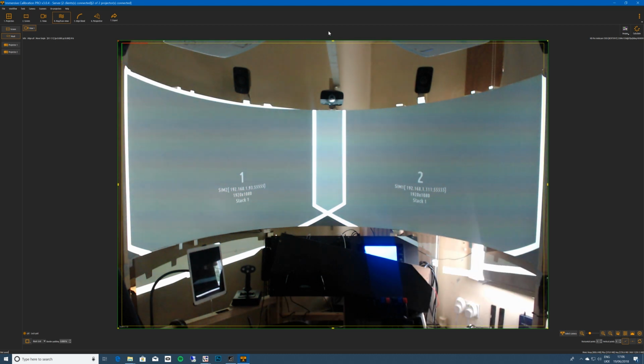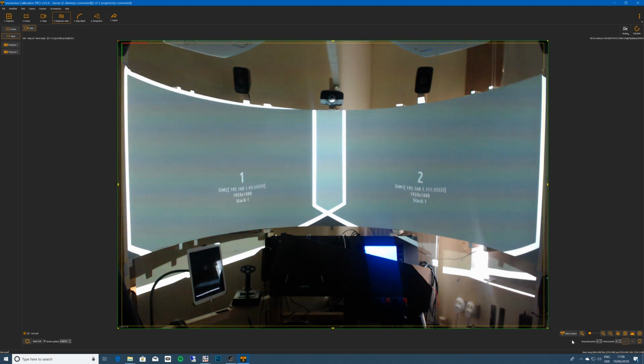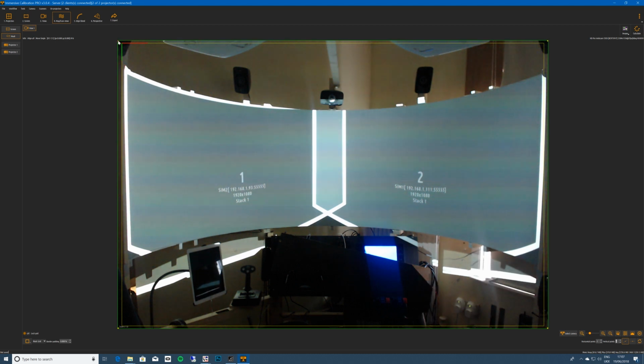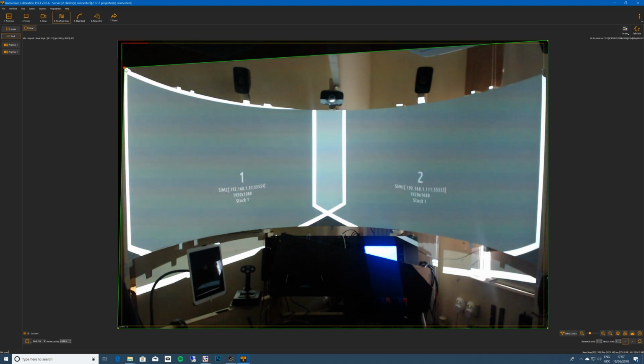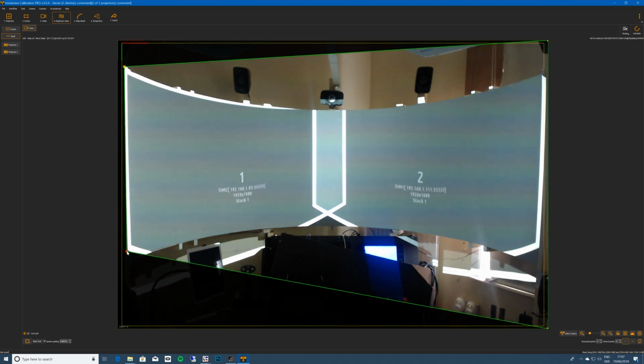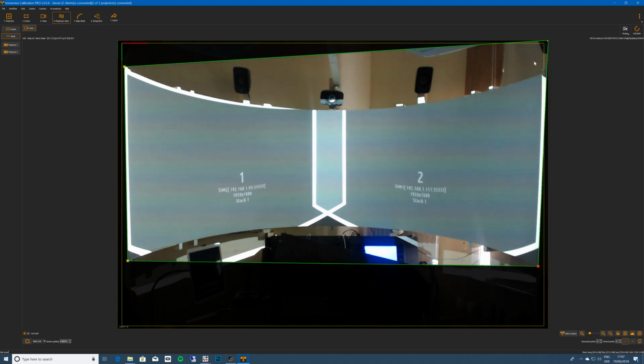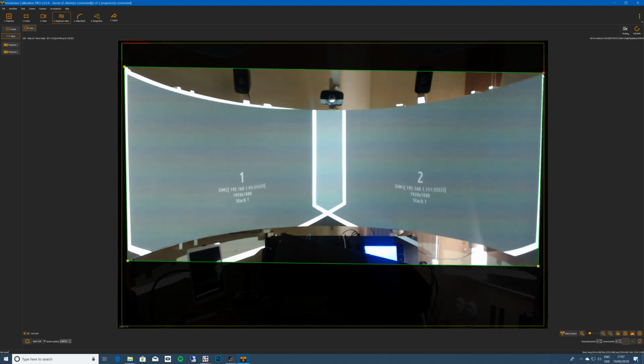Now, mask grid and all these grids are defined by a certain number of points. So you can see there's 1, 2, 3 points horizontally, 1, 2, 3 points vertically. I'm going to cut that down to 2 each. So basically, it's a square or a rectangle, and I'm just going to drag those to the edges of the projection display. About there. And remember that anything that's outside of this mask will not get used for calibration. So that looks to be about right.